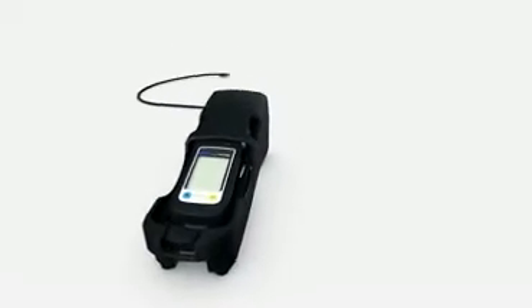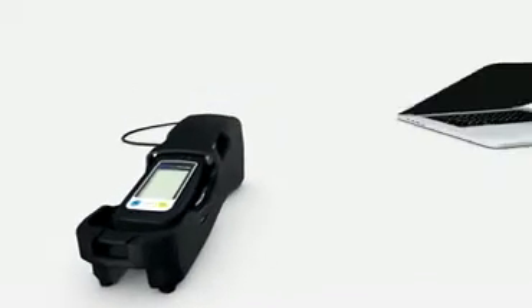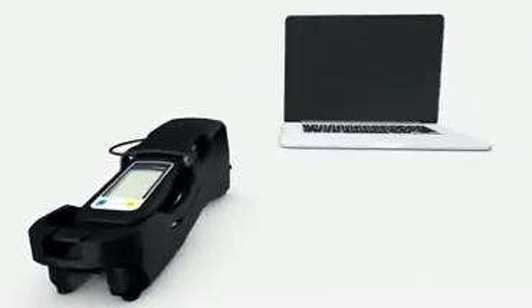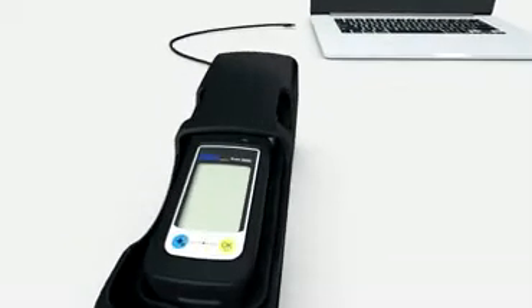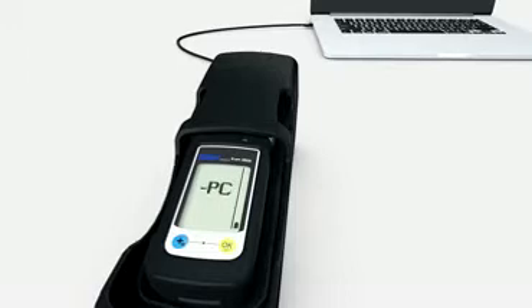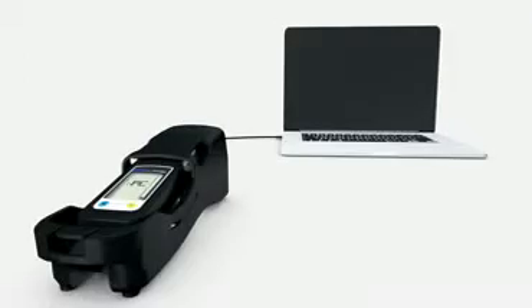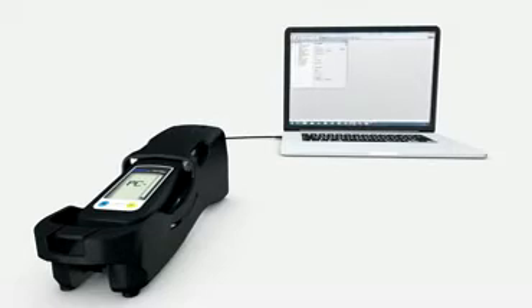The Dräger X-am 2500 has a USB infrared interface to connect the instrument to a PC. As soon as connection has taken place, PC appears in the device's display. You can now transmit or read out data. You can also change settings and alarm thresholds by using the CC Vision software, which can be downloaded from the device's product webpage at www.dräger.com.